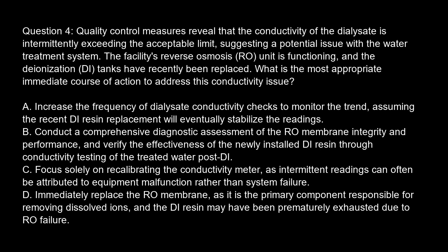Option A: increase the frequency of dialysate conductivity checks to monitor the trend, assuming the recent DI resin replacement will eventually stabilize the readings. Option B: conduct a comprehensive diagnostic assessment of the RO membrane integrity and performance, and verify the effectiveness of the newly installed DI resin through conductivity testing of the treated water post-DI.